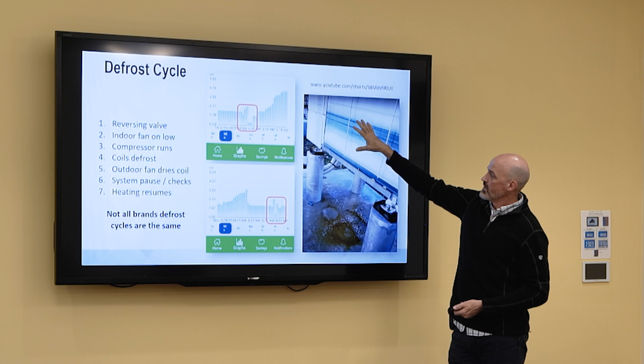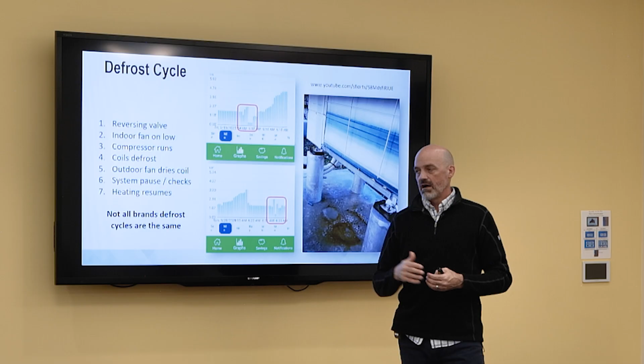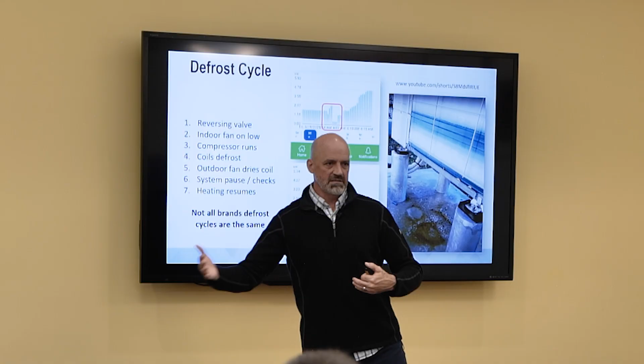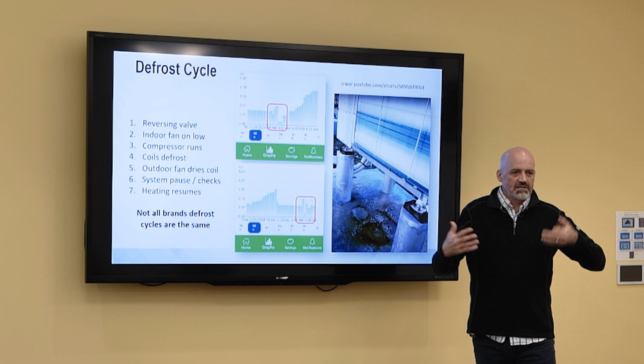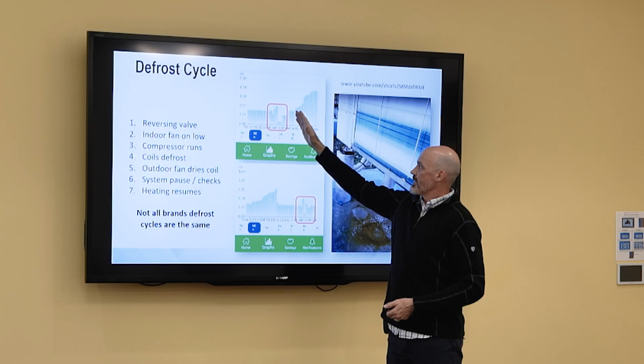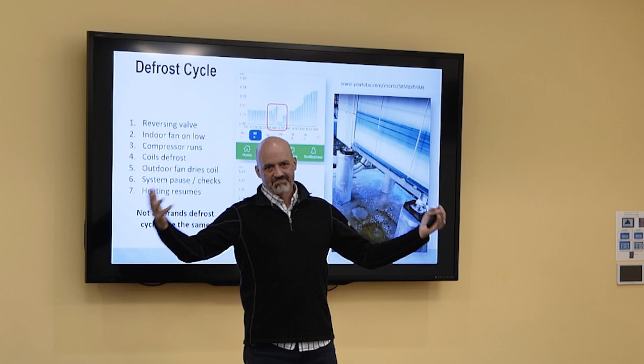Once it hits this timeout, different equipment handles it differently. Some are based on time, some on temperature. Mitsubishis are adaptive — it's like, how long since the last defrost, how long did I have to run until I saw certain numbers on my sensors. So it learns and then forgets. It's this adaptive cycle, another example of different product quality out there, like how different cars have different engineering and you get different outcomes. That's what keeps defrost relatively short for Mitsubishis and some others. But some systems just run defrost for 10 minutes regardless, which starts to really impact the amount of heat delivered into the house over the design day.